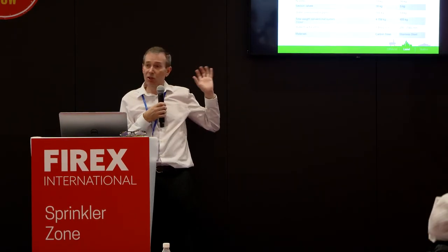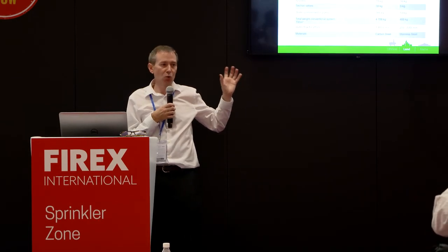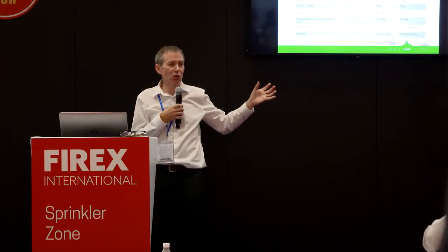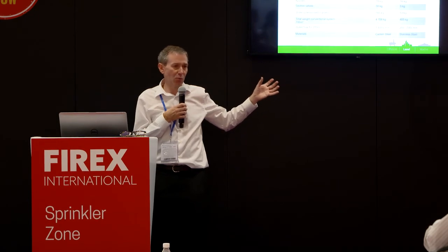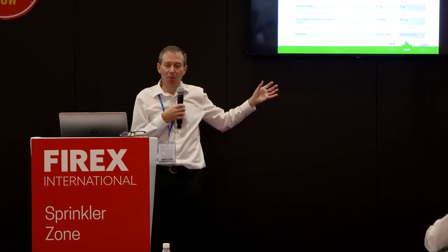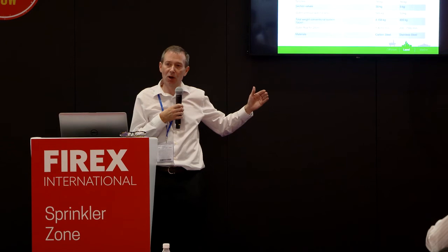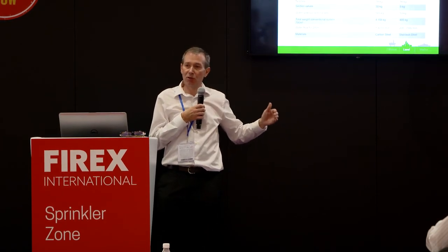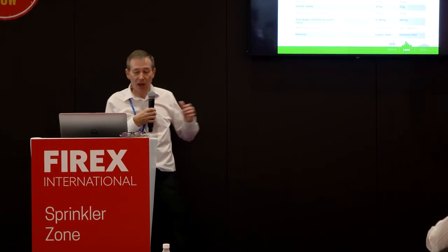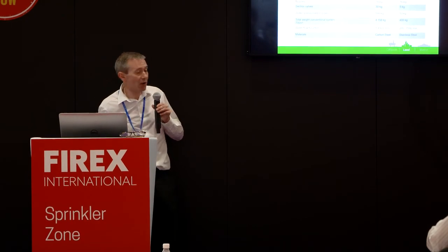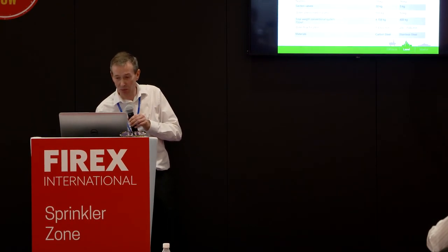Saying that, this system will never replace sprinklers. This is an alternative, a different solution to dealing with and suppressing fires. It's not a replacement. It never will be, because there will always be scenarios where water mist is better than sprinklers and sprinklers are better than water mist. But that gives you a very good overview of water mist systems.